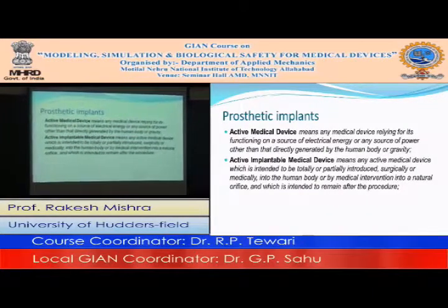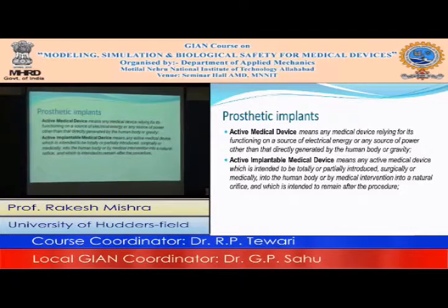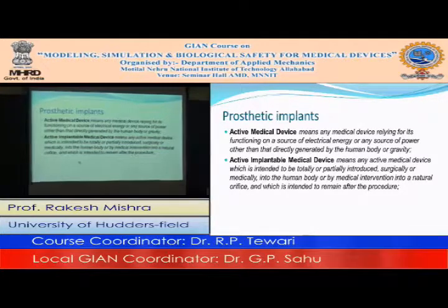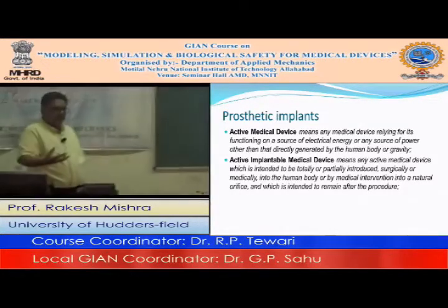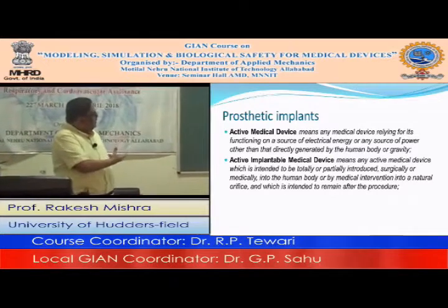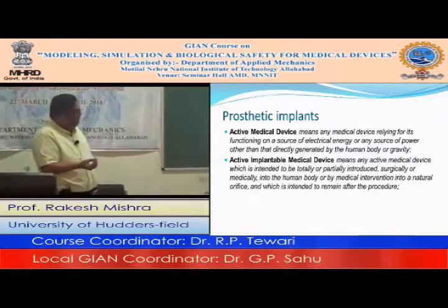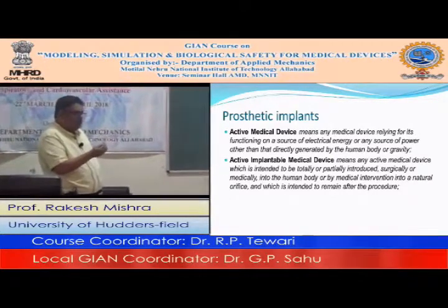Now, with regard to prosthetic devices, I must mention two terms which will come in our discussion in future: active medical devices and active implantable medical devices. An active medical device is a device which needs energy for its functioning, and that source of energy is from outside.